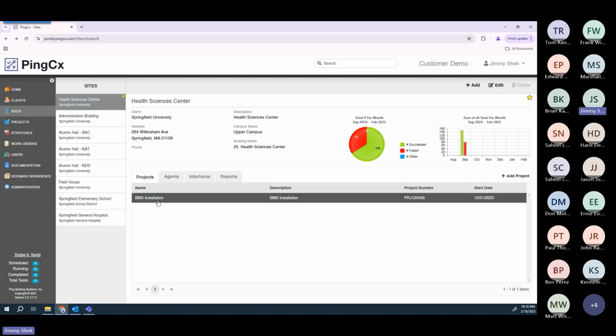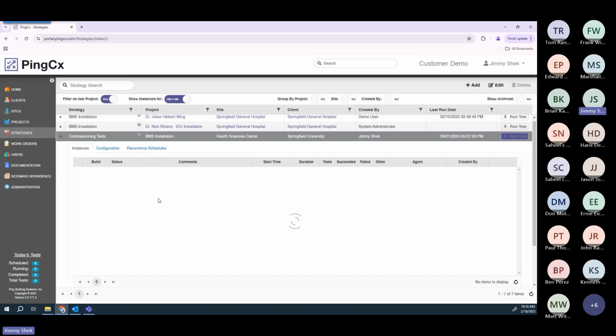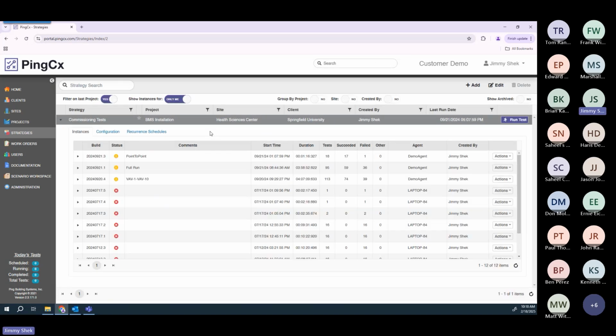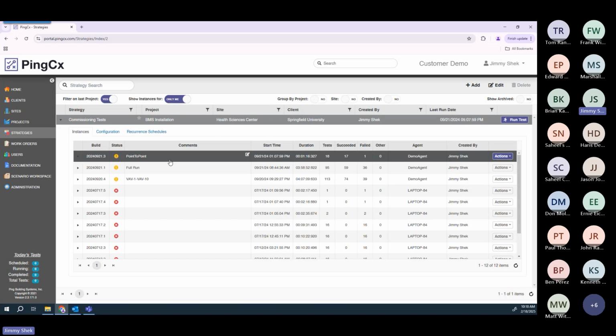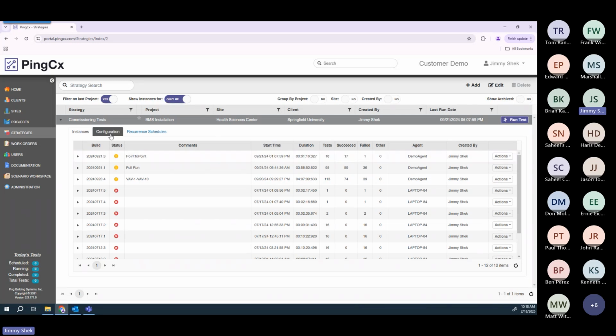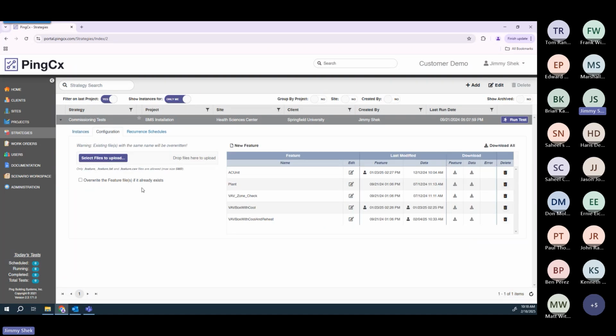Okay, so I'm going to drill into the projects and ultimately the strategies here. On the strategy screen, you'll essentially see a historical listing of all the test runs that were completed for that particular site/project. But before you can schedule a job, you need to create what we call feature files. As I mentioned before, the feature file is a collection of test scenarios that get run against the BMS system. So typically, there's a feature file for each type of unit. In this particular example, we have one defined for the AC unit, one for the main plant, and some for the VAV boxes.